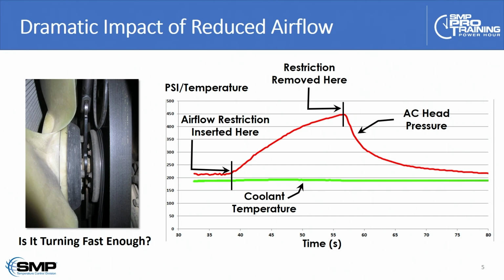Within about 15-20 seconds, we got from 220 psi to about 450 psi. Right at the top of the red trace is where we pulled out the cardboard, and you can see that within 15-20 seconds the high side pressure went back down again, pretty dramatically, pretty rapidly. The green trace is engine coolant temperature, again directly from the scan tool. You can see that it's basically flatline, unaffected, around 200 degrees.